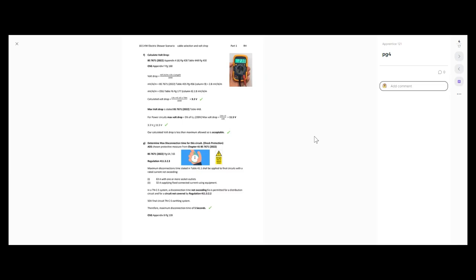Next we need to verify that the volt drop on that cable is going to be within the maximum permitted — either by the manufacturer of the equipment, or if we don't have that information, we can go with the regs. We can find all this information on volt drop within Appendix 4 of the regs on page 428 and table 4AB on page 430, or in the on-site guide Appendix F on page 168. The on-site guide gives us the formula to calculate volt drop, which it doesn't in the regs. To calculate volt drop, we need to know our millivolts per amp metre for the cable selected, times our design current, times our length, divided by a thousand to get volts.